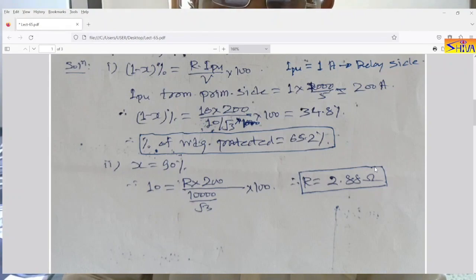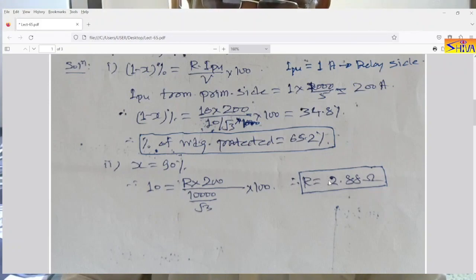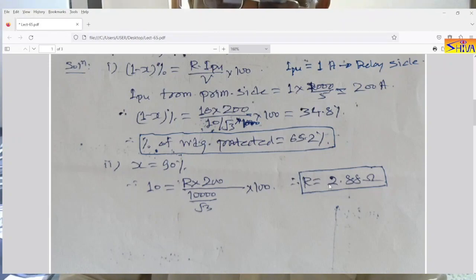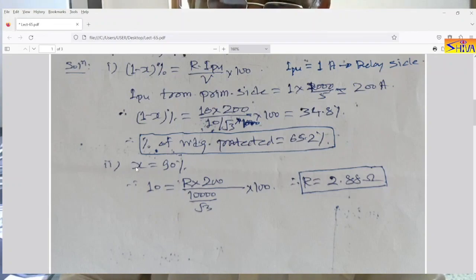So here you can see that if we reduce the value of resistance, the percentage of winding protected will increase. In the first case the resistance was 10 ohms and the winding protected was 65.2%. In the second case, resistance has drastically reduced to 2.88 ohms, so the winding protected is 90%.